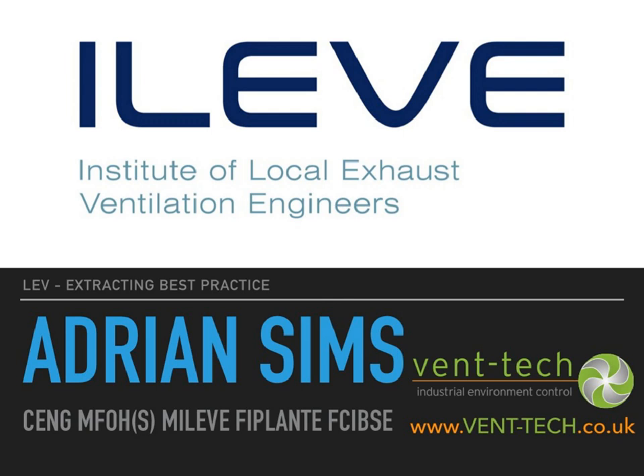The first question that's popped up is, where can I find guidance about the exhaust stack velocity for an LEV system? Discharge velocities from stacks are made up of a number of things. It's not just the rise due to momentum, which is the velocity, it's also the rise due to buoyancy of the gases you emit. The physical stack height also makes up part of it, and you then get what's known as wake downwash - this is the wind coming around the stack causing turbulence and dragging the fumes back down.